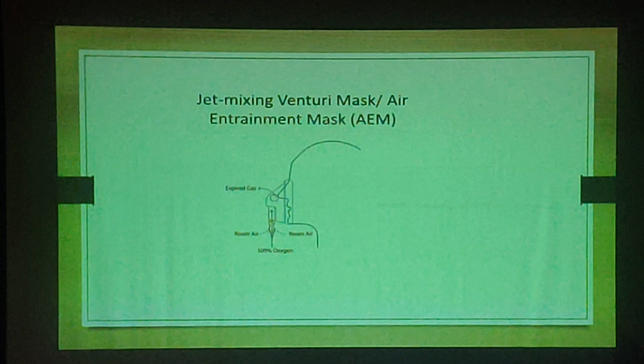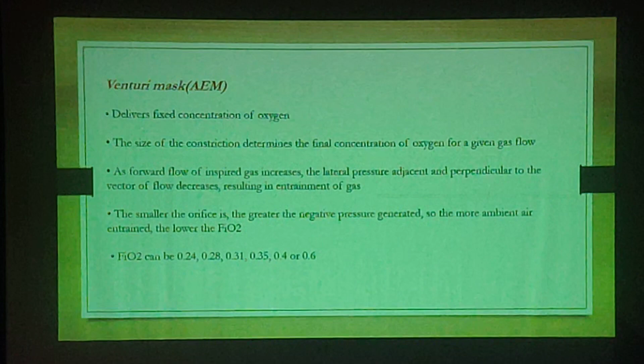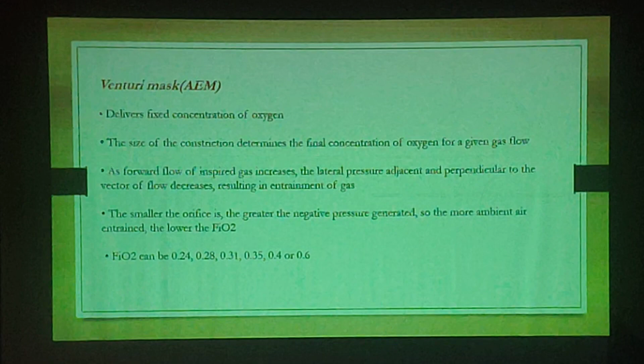So there are various types of Venturi masks: the jet mixing Venturi masks or the air entrainment masks. They deliver a fixed concentration of oxygen. The size of the constriction determines the final concentration of oxygen for a given gas flow. A forward flow of inspired gases increases the lateral pressure as explained, and by that the entrainment of air occurs. The smaller the orifice, the greater the negative pressure generated and the lower the FiO2.